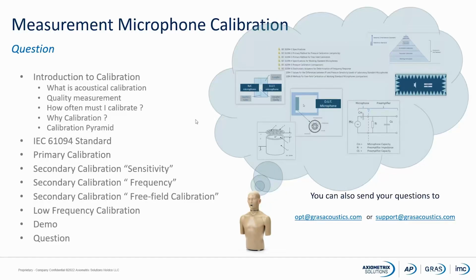No, actually not. For sensitivity calibration, you need, of course, to have an adapter for your piston phone, so it will fit into your piston phone. For the frequency part of it, when you buy an electrostatic actuator, the RA0014, then an adapter for a 1/8 inch microphone is actually included. Of course, the level of a 1/8 inch microphone is very small because the 1/8 inch microphone has a very low sensitivity, so you might have some noise, electrical noise, background noise in your room, which you have to take into consideration, but else it is actually straightforward.